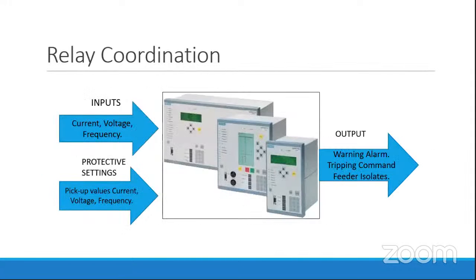Whenever we set these relays at a particular value, for example, if we set the current for this relay as 10 ampere, then in a faulty condition this current will rise much higher than this 10 ampere. Then the value will cross this threshold value. At that time, the numerical relay will give a pickup, issue a tripping command to the circuit breakers, and isolate the system.